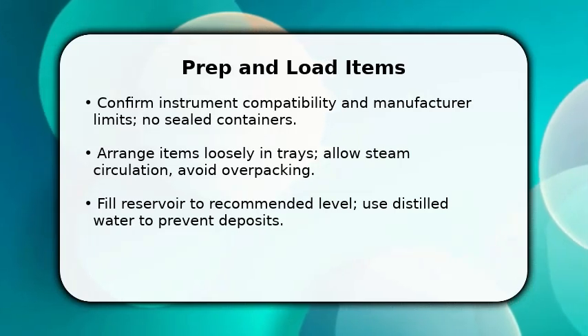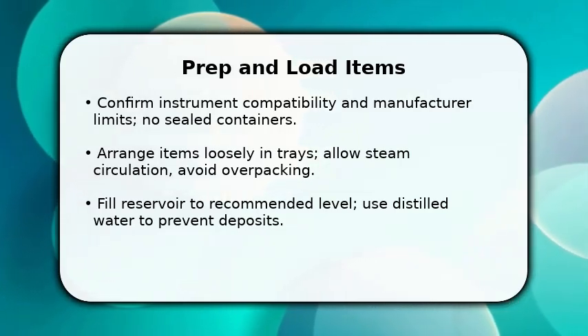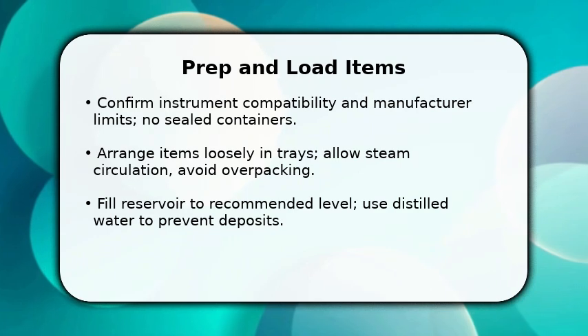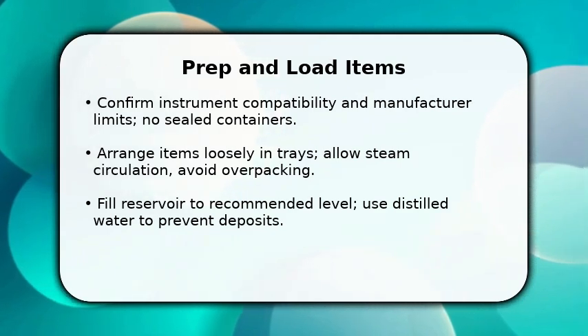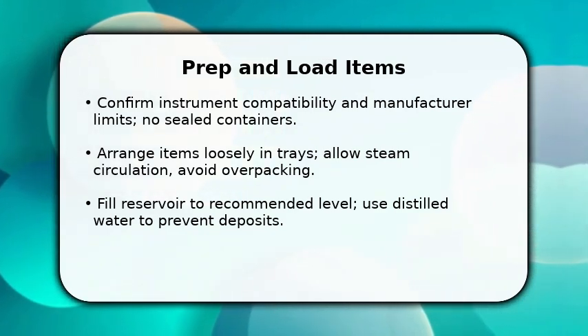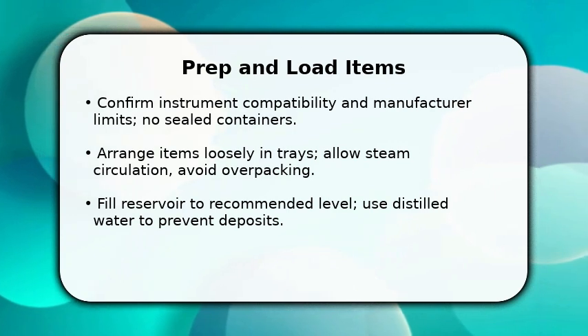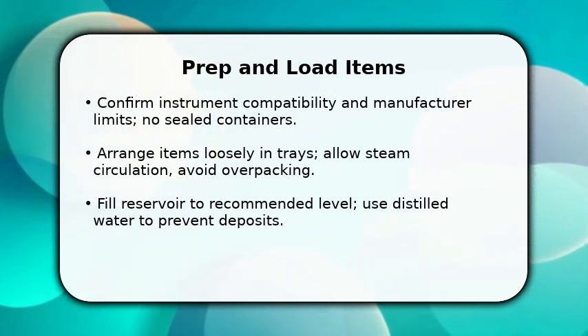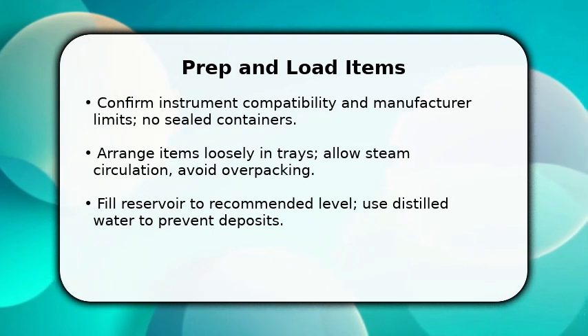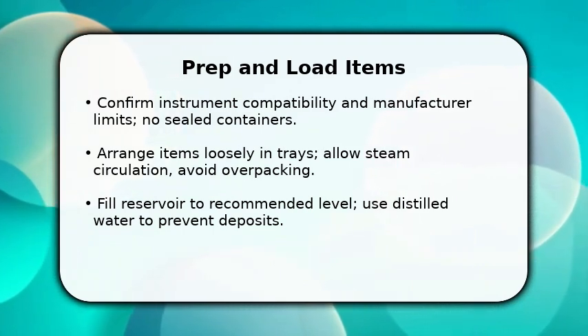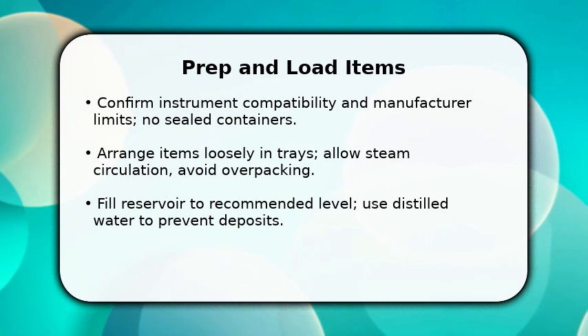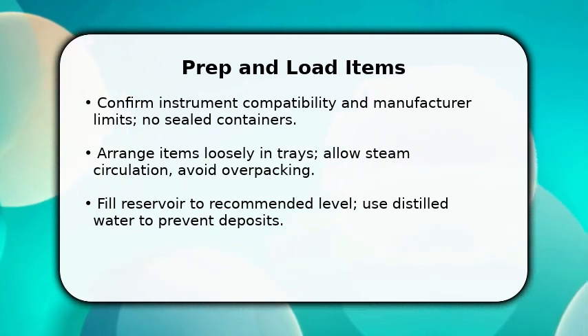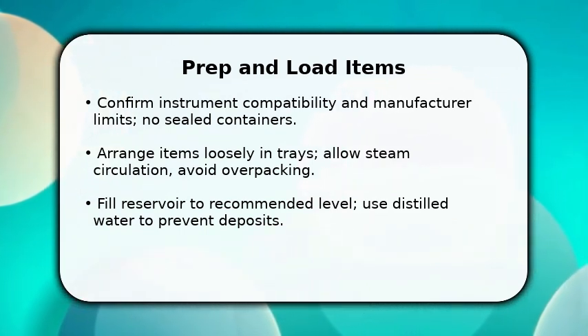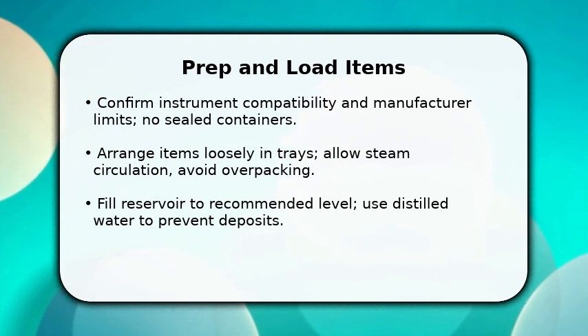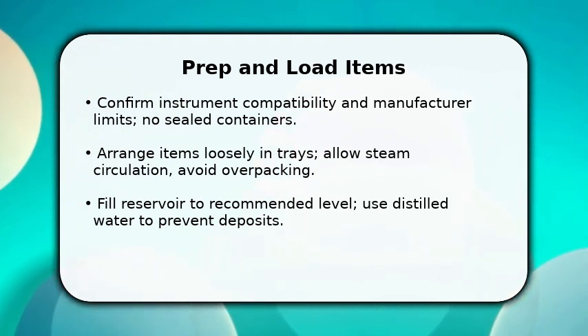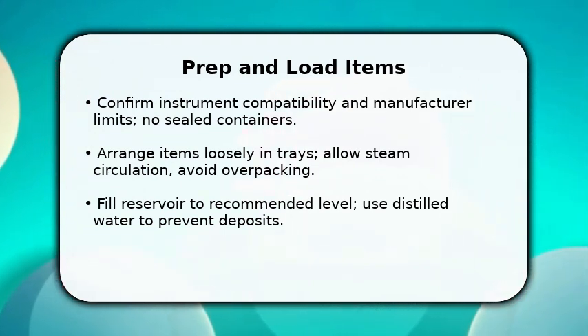You start by confirming instruments are autoclave safe and manufacturer approved. This prevents damage and ensures sterilization. Once verified, load trays loosely so steam can reach all surfaces. Stacked or sealed items trap air. Make sure the reservoir has the correct amount of distilled water. This prevents scale and maintains proper pressure. Close the door and latch firmly. You're now ready to set temperature and time. These first actions establish conditions for reliable sterilization.